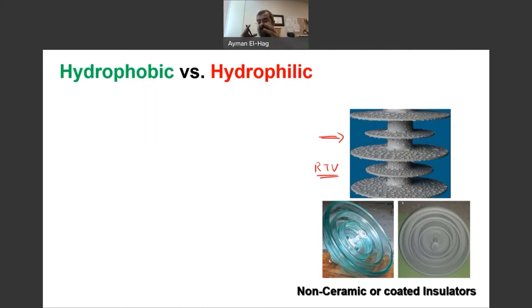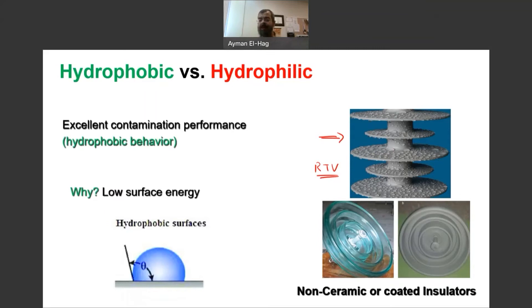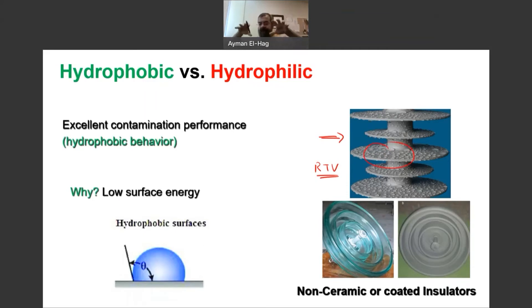So when we have this material, as you can see here, the water droplets don't come in contact with each other. This is what we call hydrophobic behavior. This material has a hydrophobic behavior, which is the opposite of ceramic insulators — the surface energy is very, very low. So if a water droplet comes onto the surface, it results in a very high contact angle, giving you discrete water droplets that are not connected with each other. There is no wetting layer, so there is no path for the leakage current.